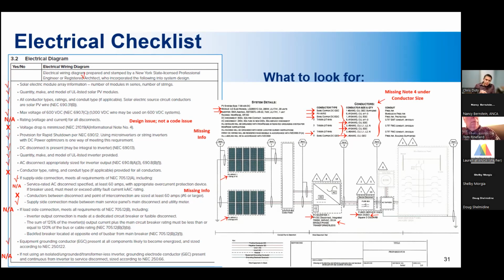And one thing to keep in mind is there is a difference between a code review and a design review. For instance, a design issue may be if a disconnect switch is not labeled for the voltage or the DC rating, but that may not be a code violation yet. So you would verify that during the actual inspection when you see what's actually on site.